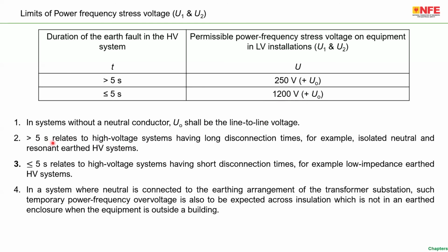So greater than 5 seconds relates to a high voltage system having long disconnection time, for example, isolated neutral or resonant earthed system. Less than or equal to 5 seconds relates to a high voltage system having short disconnection time, for example, low impedance earthed system or directly earthed system.